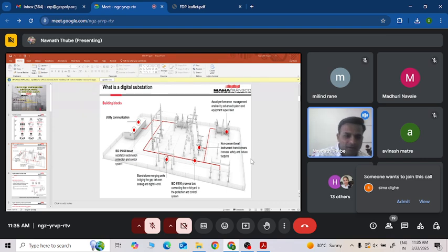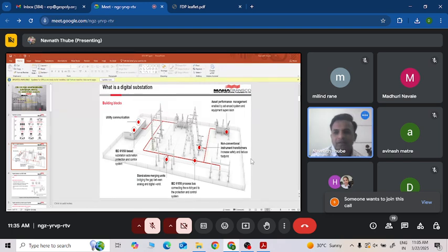This is another SLD regarding digital substations. These are all conventional equipment. Then this is a process bus. After the process bus, the data goes onto the common bus, and from the common bus we can monitor it through our utility center. This is actually the main thing in a digital substation.